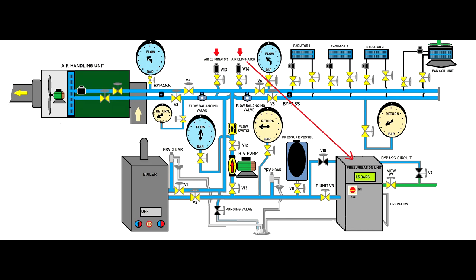While the heating pump is running, I think in an installation you'll always have here and there small pockets of air which will be cleared, and the air eliminators will be active most of the time. So the pressurization unit will push water in the system to compensate the volume loss by the air elimination. So you don't have to worry for the first day if the pumps will run a little bit excessively until the air will be cleared from the installation.